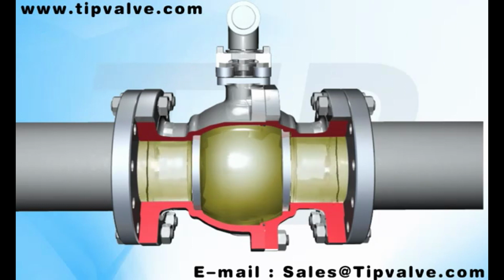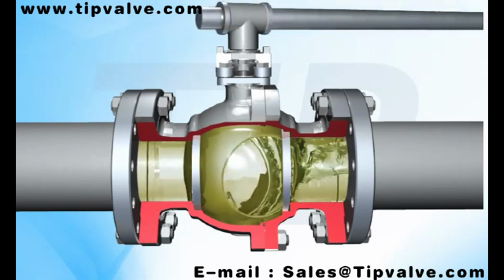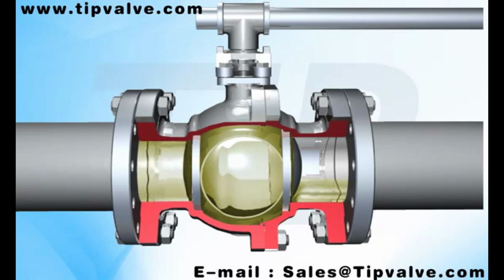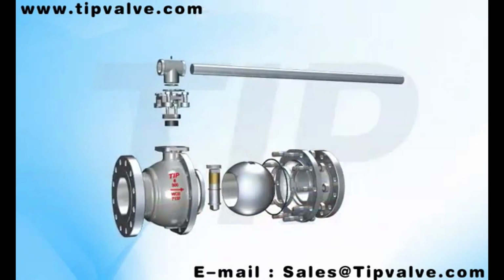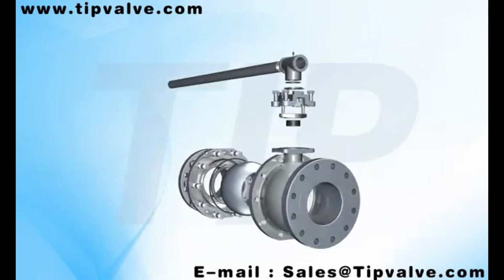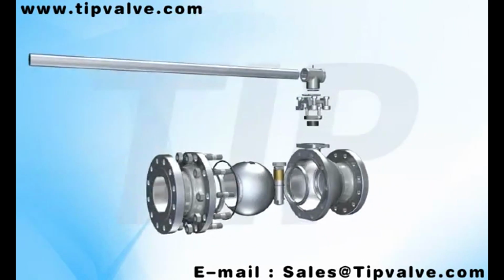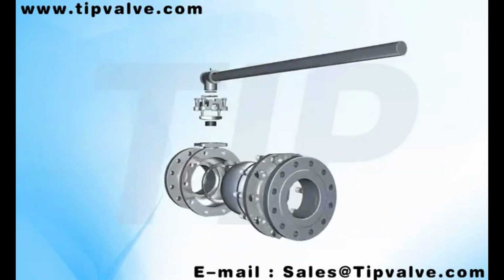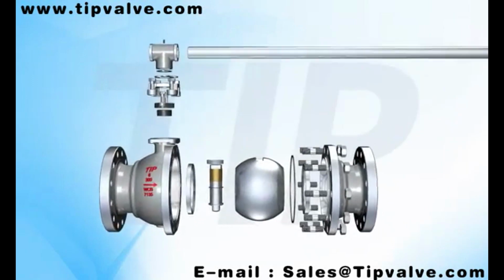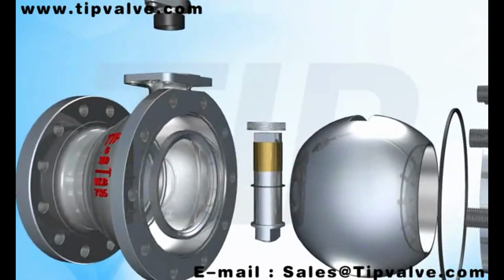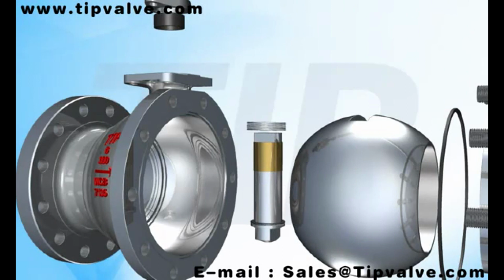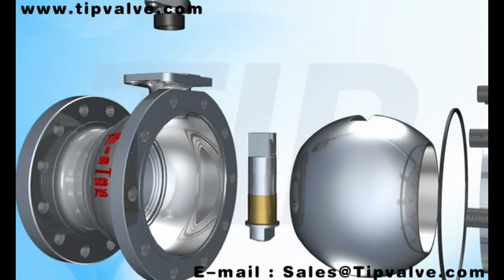When the medium pressure is small, the contact area between its gasket ring and ball will also be small. So the seal specific pressure will be big in that contact area to ensure a reliable seal. When the medium pressure is big, the contact area between its gasket ring and ball will also be big. So the gasket ring can bear a large medium thrust without being damaged.